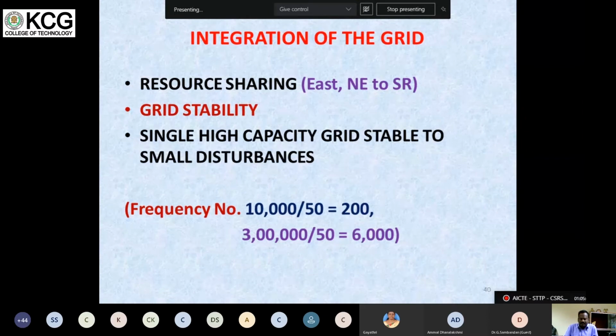But if a grid is a total combined 3 lakh megawatt grid system, only after a 6,000 megawatt failure will the grid frequency go down to 49 Hz. That is an advantage of this integration of grid. Not only resource sharing, resources can be shared from other regions to the less resource region. Then grid stability can be obtained by integrating the grid system. So these are the main reasons why we go for integration of the grid: resource sharing, grid stability, and the frequency number.